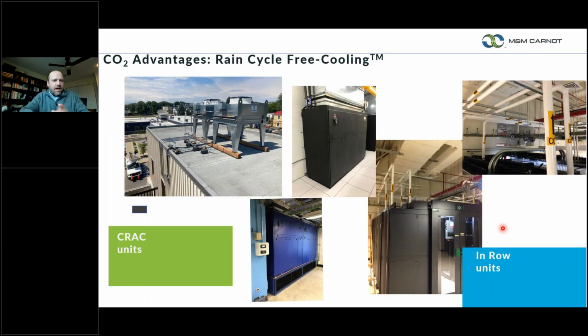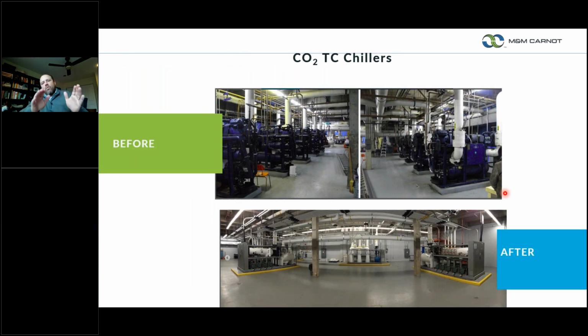Just some more photos, showing upflow, downflow, our gas coolers, the one that I showed you before, but also our row-based equipment in pod format. Up here on the right, it's a nice photo because we get to show the simplicity of the CO2 piping going into our row-based cooling modules. Where I was telling you about the capacity or the amount of heat that CO2 can hold, you require less gas, which actually makes the pipe smaller than what you would see in a normal synthetic refrigerant-based system.